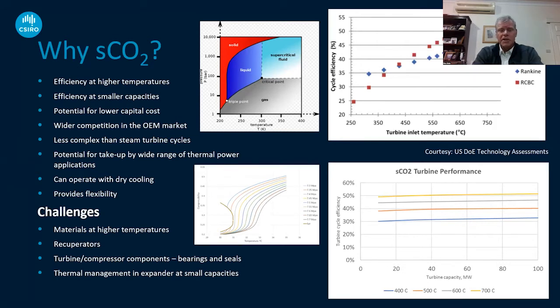Particularly high efficiency at higher temperatures. You see in the top right-hand curve that the crossover point between a subcritical Rankine cycle and an RCBC supercritical CO2 turbine is noted at about 450 degrees. I actually think it's more like 550 degrees Celsius where that crossover occurs. But at higher temperatures, you get higher efficiencies from the supercritical CO2 cycles.